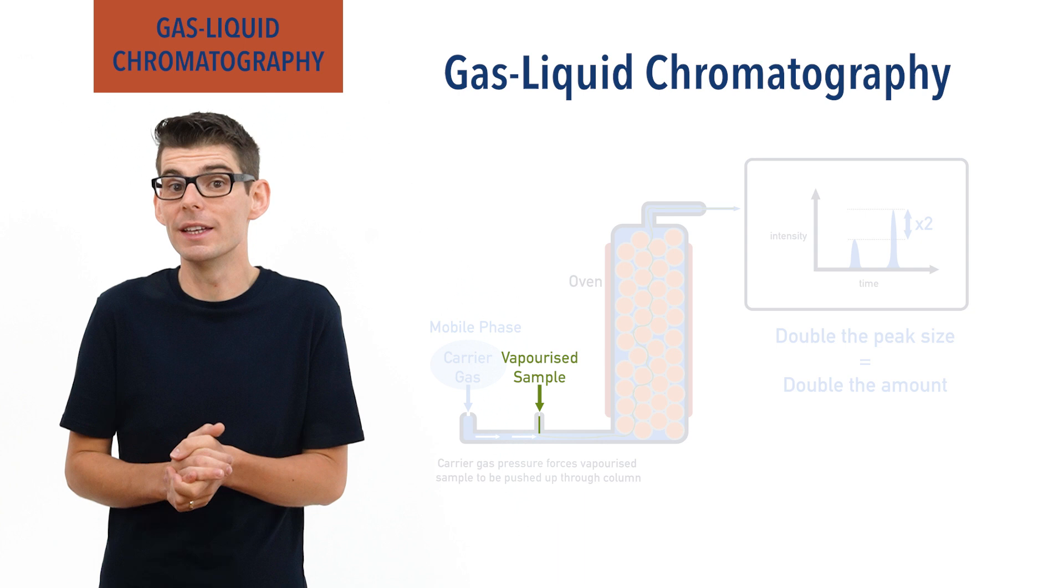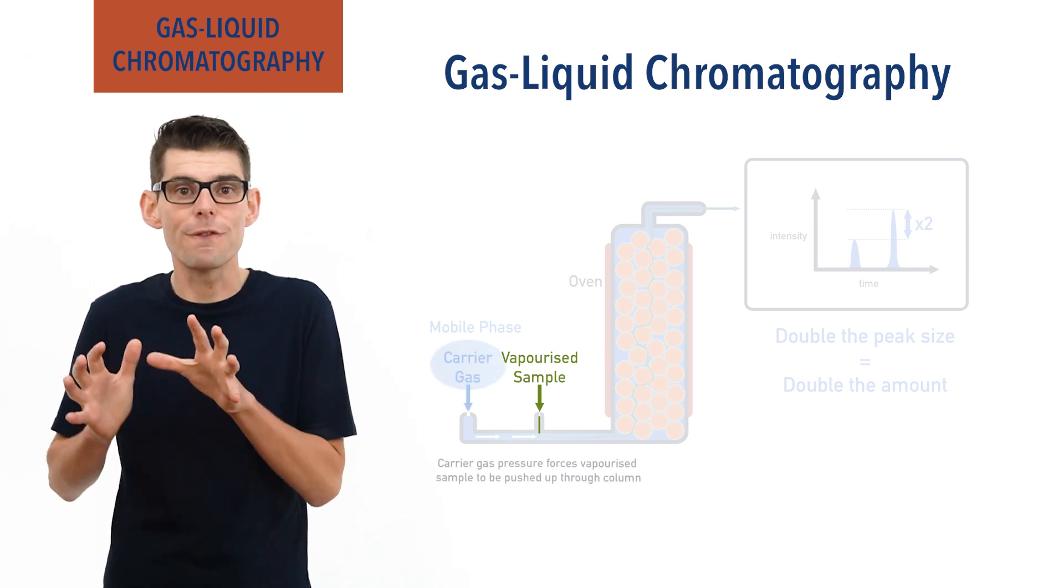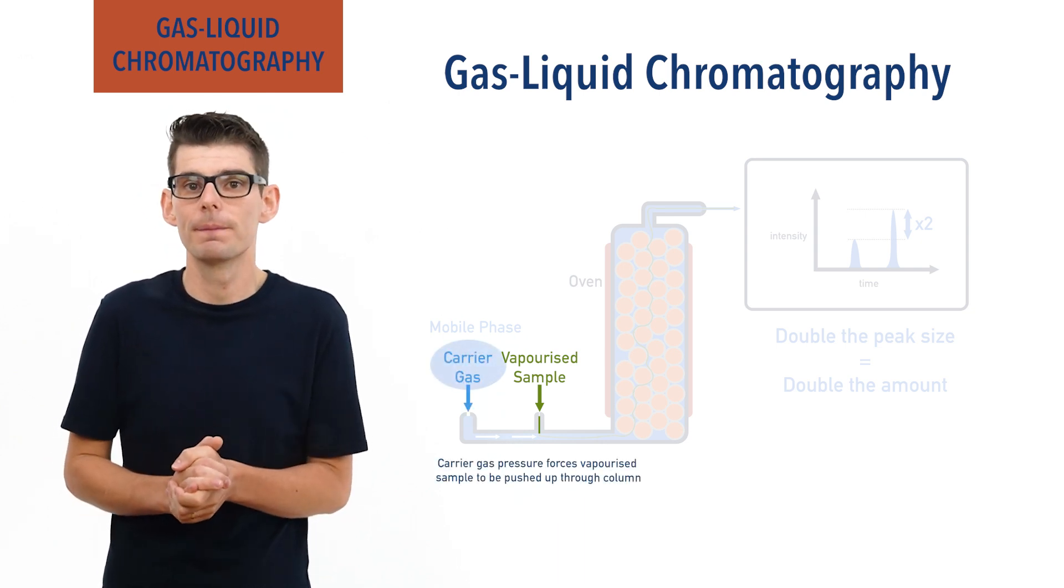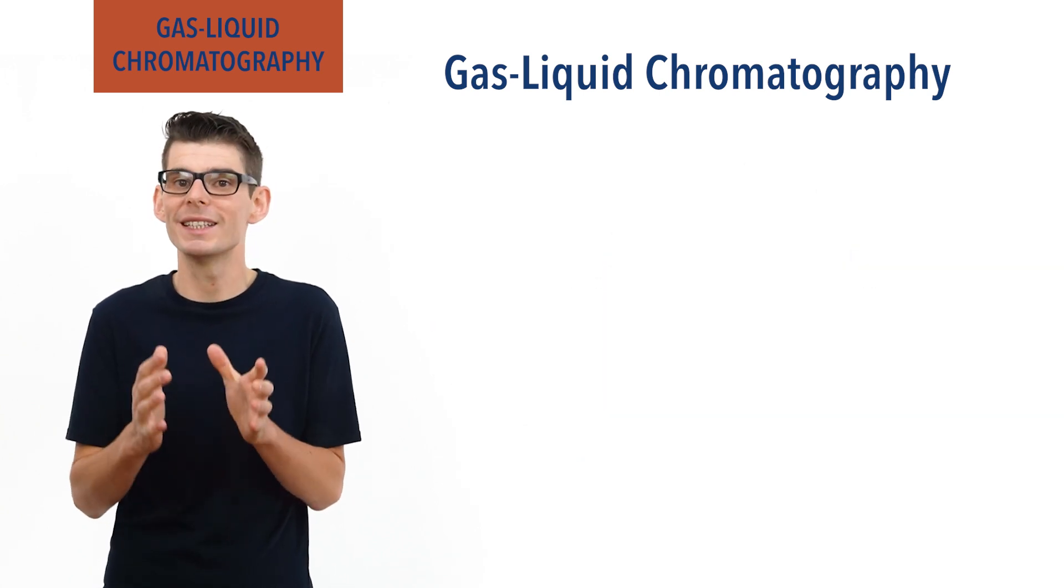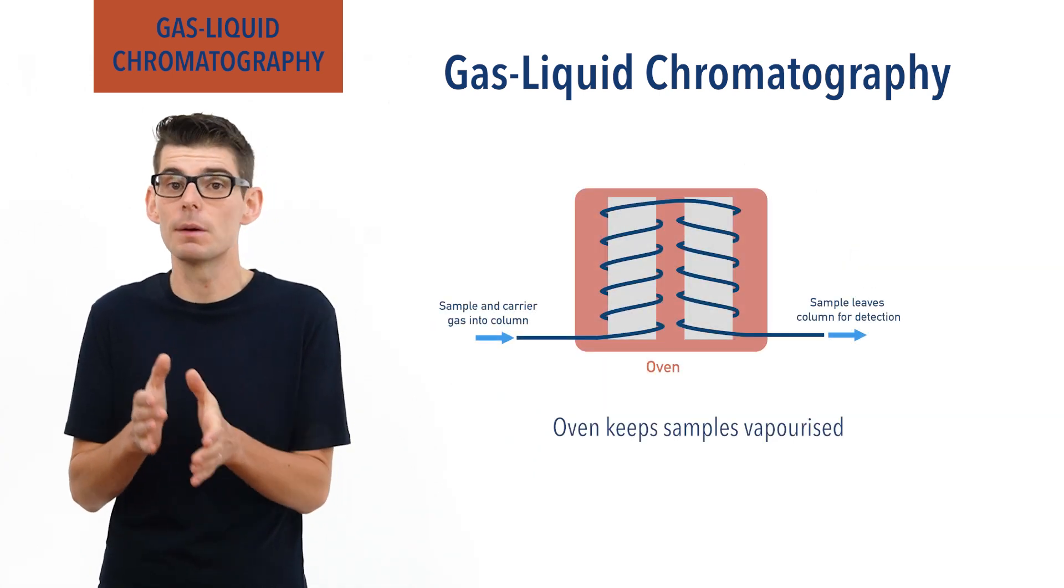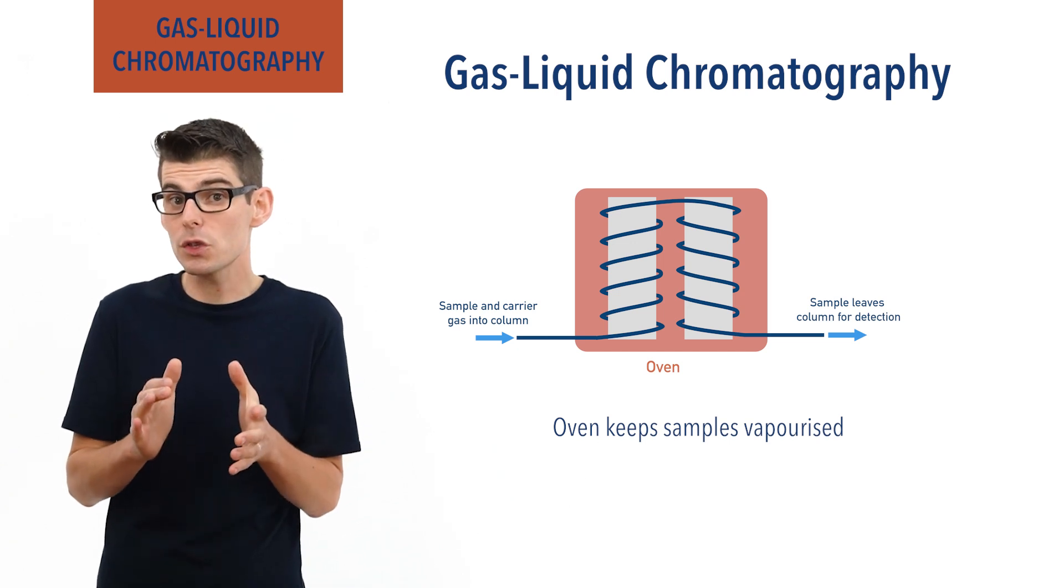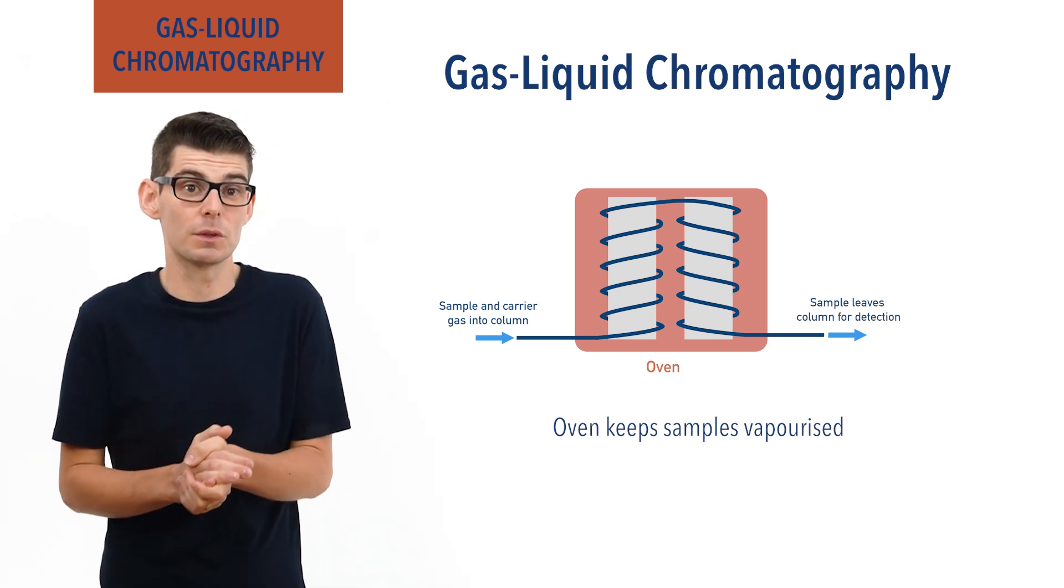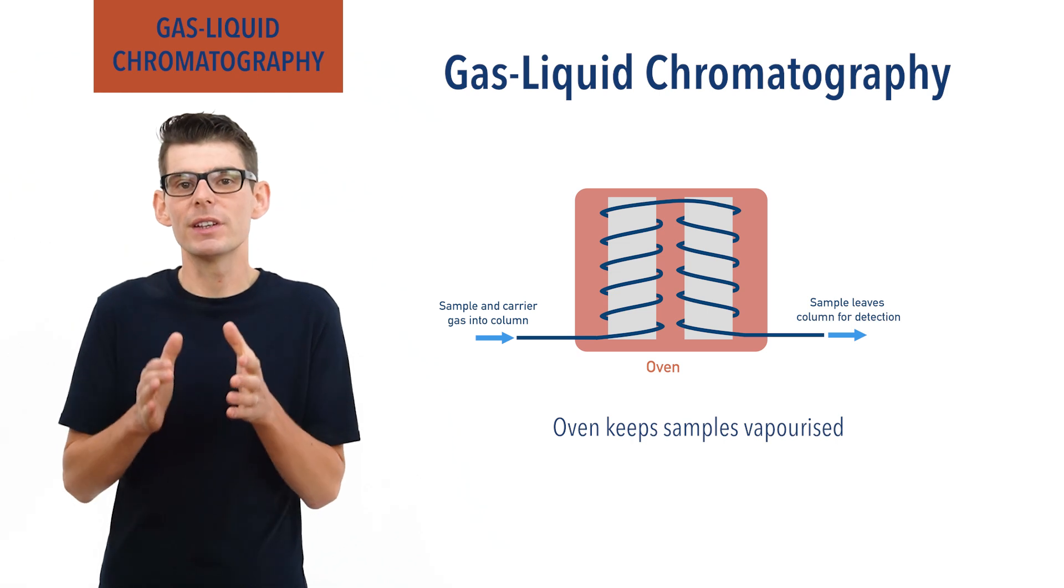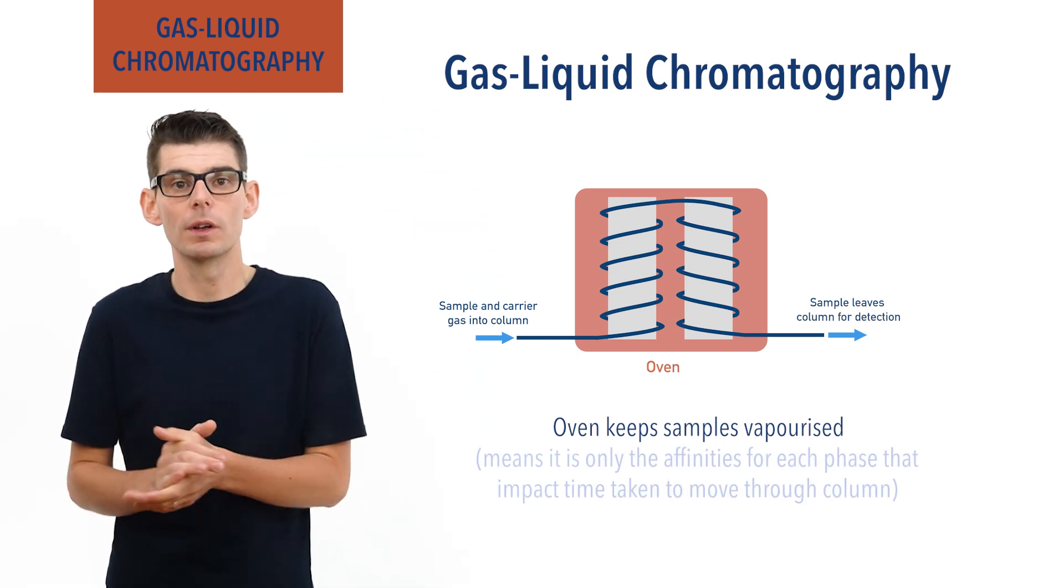As we mentioned, the inert gas is under pressure forcing it through the column. To ensure the sample stays vaporized, the column is coiled inside an oven to keep the sample boiling. This ensures it's the affinity for each phase and not simply the physical state of the substances that determine how long it will take them to move through the column.